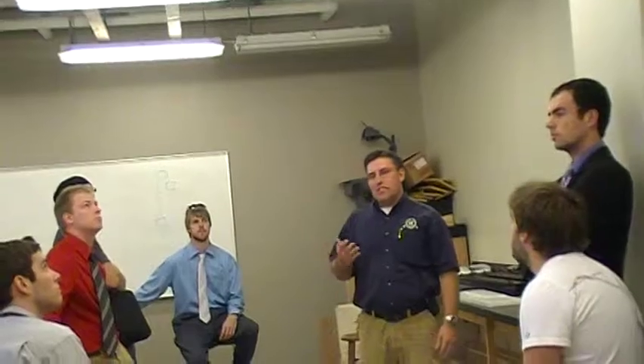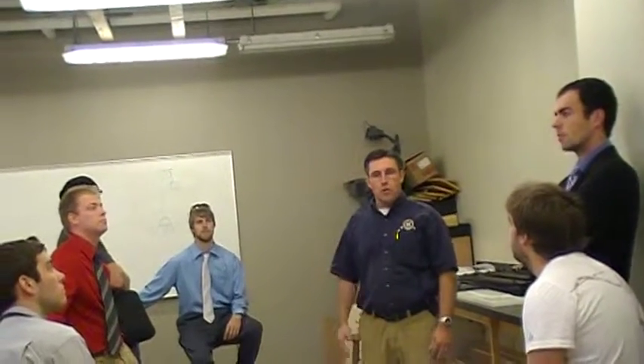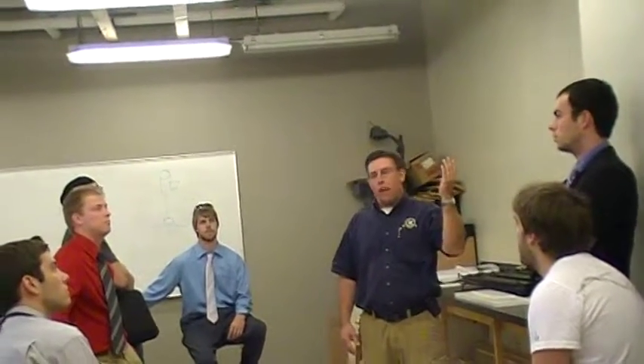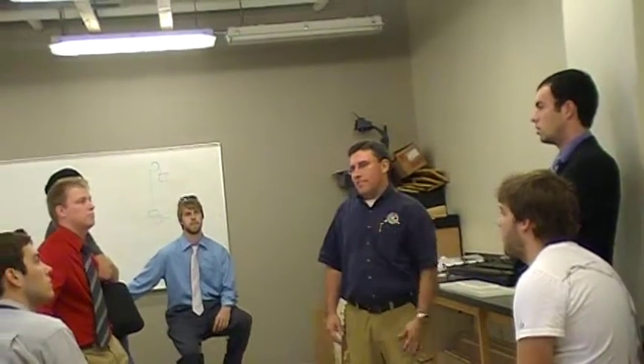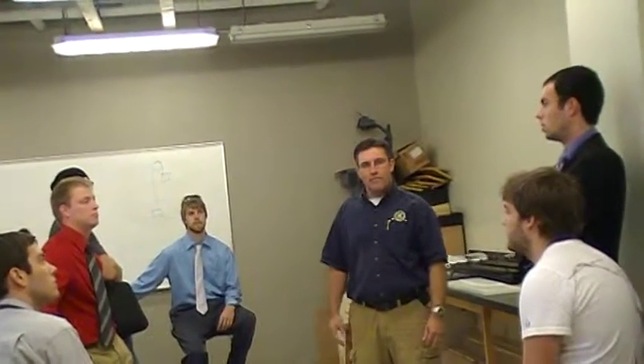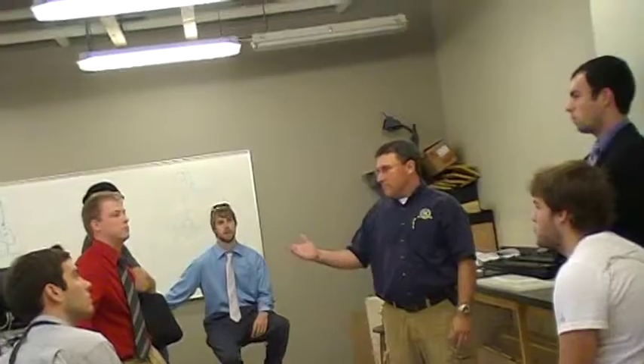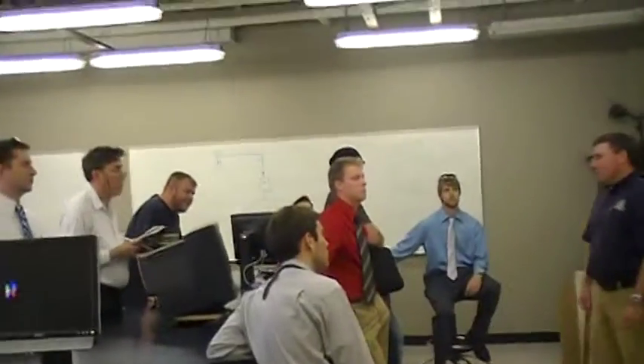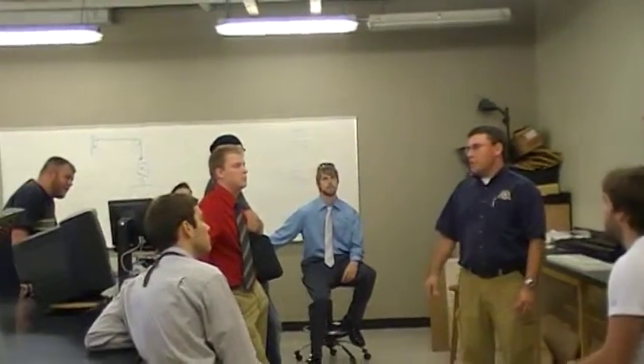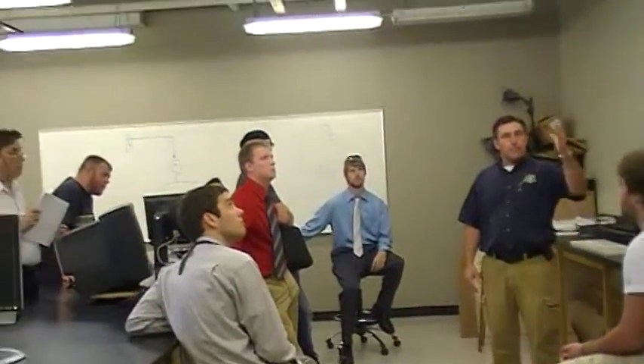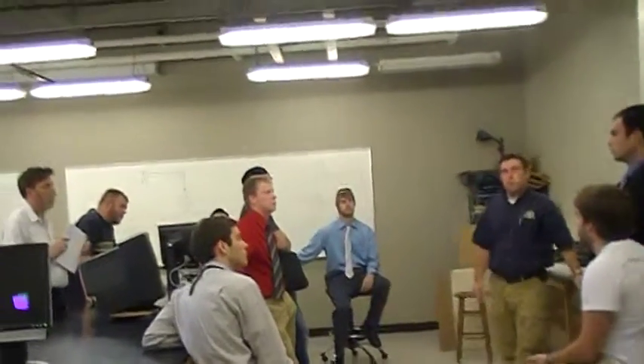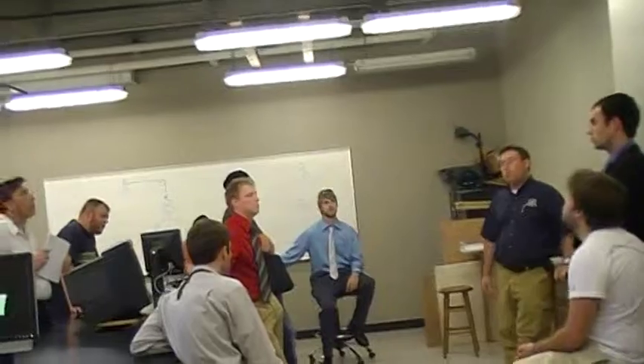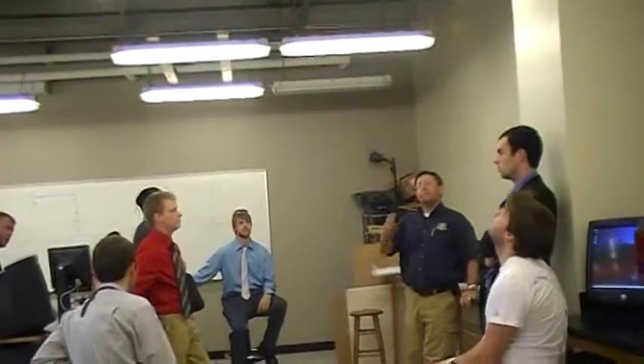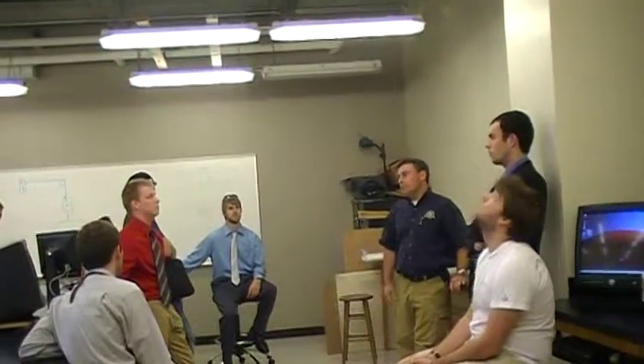55-degree air. Does anybody know why the air is so cold? Why are we just not running at 72 degrees? Why we're running at 55? We're taking moisture out of the air before it gets here. So at the air handlers that we'll go see in the attic, that's what we're doing there. Removing the moisture, and then we'll reheat it here.